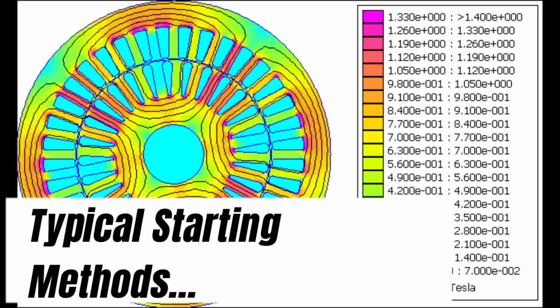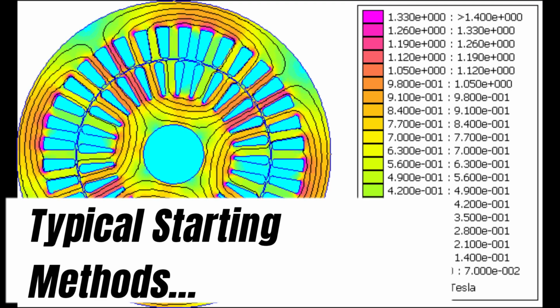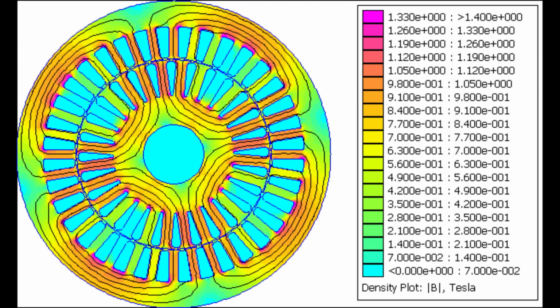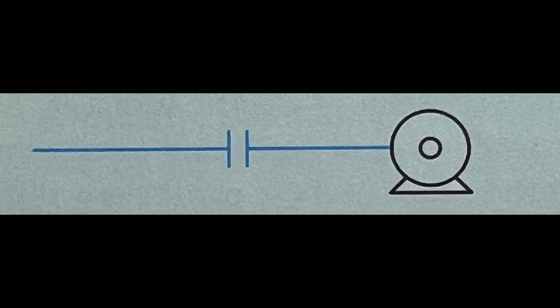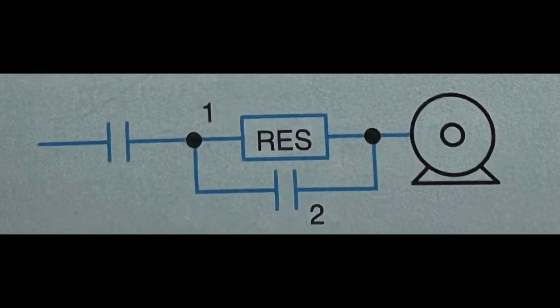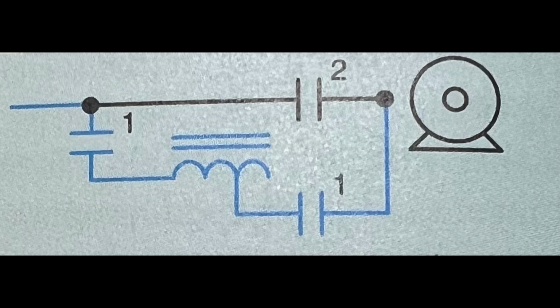Typical starting methods. Starting methods for polyphase motors. The most common methods for starting polyphase squirrel cage motors include, first, full voltage starting, where a hand-operated or automatic starting switch throws the motor directly across the line. Next, primary resistance starting. A resistance unit connected in series with the stator reduces starting current. Next is auto transformer or compensator starting. Manual or automatic switching between the taps of the auto transformer gives reduced voltage starting.